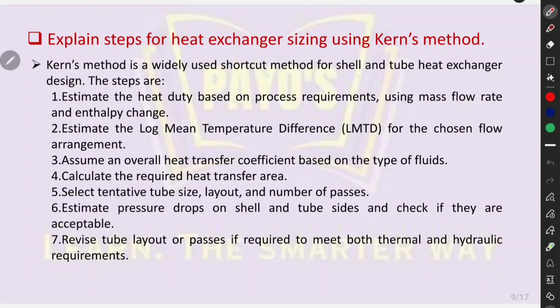Tell me the steps for heat exchanger sizing using Kern's method. Kern's method is a widely used shortcut method for shell and tube heat exchanger design. The steps are: first, estimate the heat duty based on process requirements using mass flow rate and enthalpy change. After that, estimate the log mean temperature difference (LMTD) for the chosen flow arrangement. Then, assume an overall heat transfer coefficient based on the type of fluids. Next, calculate the required heat transfer area. After that, select tentative tube size, layout, and number of passes. Then, estimate pressure drops on shell and tube sides and check if they are acceptable. Finally, revise tube layout or passes if required to meet both thermal and hydraulic requirements.